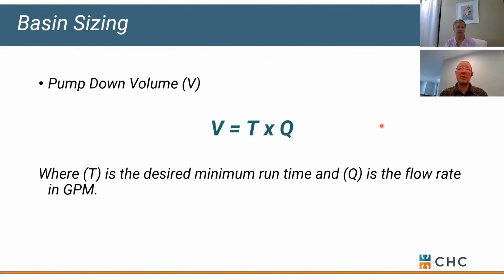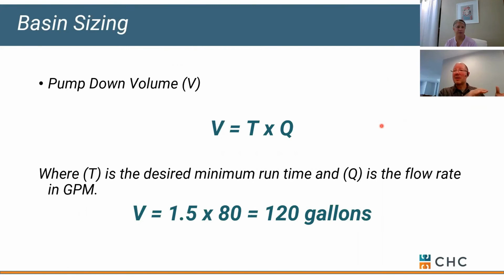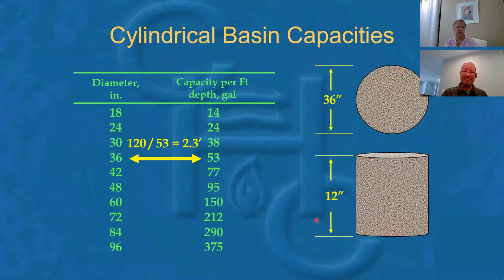What I'm trying to figure out is how much usable water I need. We can make a formula look good, but basically, if I have a potential for 80 gallons a minute to come into my basin, and I need my pump to run for a minute and a half, I need 120 gallons of usable water in my basin. That's all we're trying to do. If the pump runs longer than a minute and a half, that's fine. Now, there are basin capacity charts, based on a foot of depth for a given diameter. If I look at a 36-inch diameter basin, it holds 53 gallons per foot, but I need 120 gallons of usable. So all I'm doing is taking 120 gallons and dividing it by 53 per foot to figure out how much usable water depth I need. In this case, 2.3 feet, which is, what is that? 27 inches.